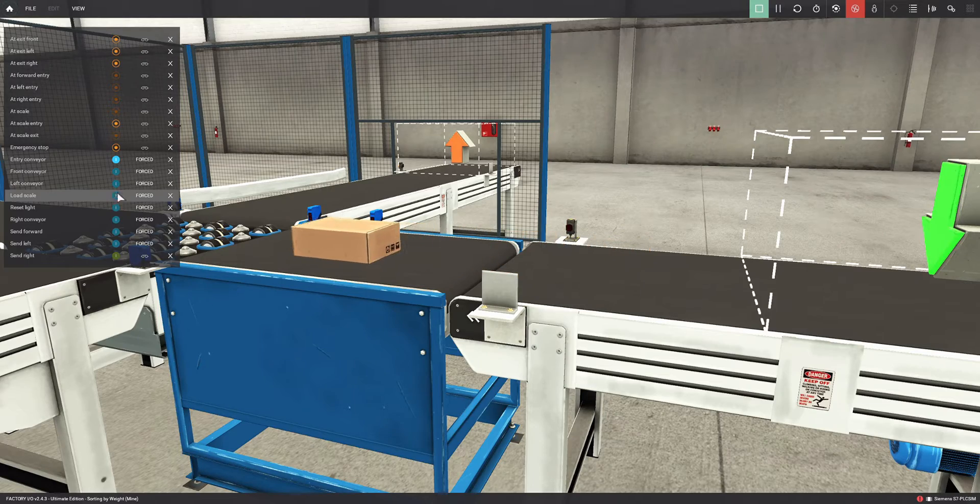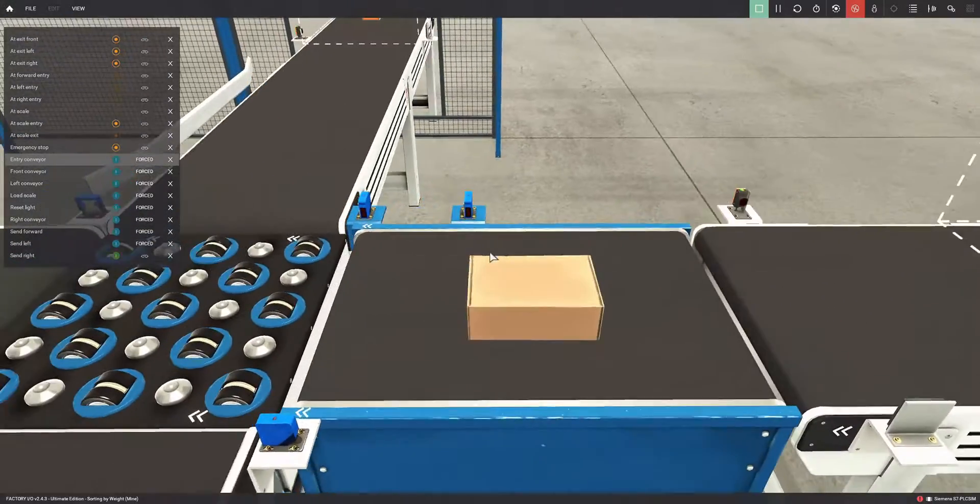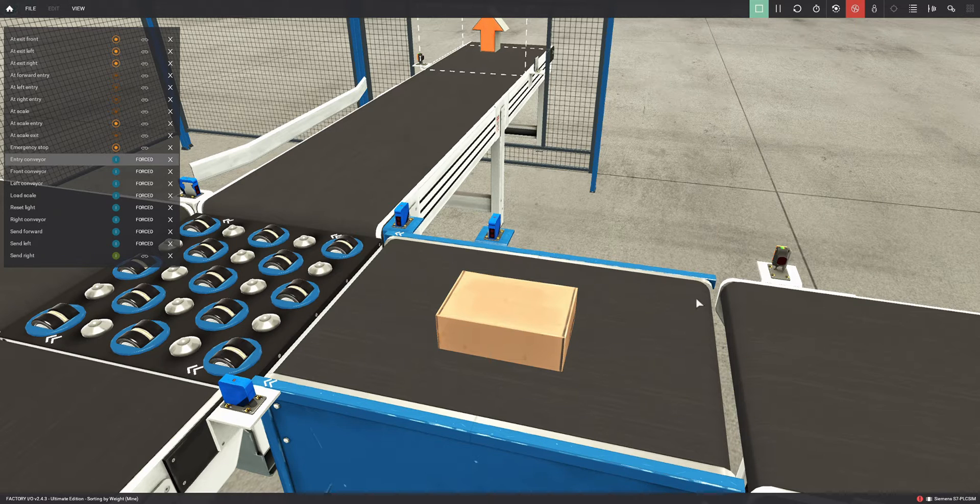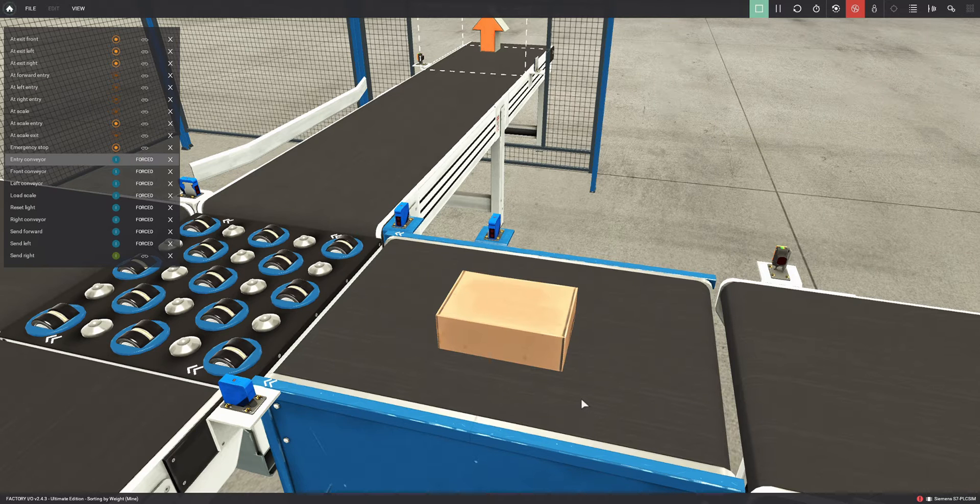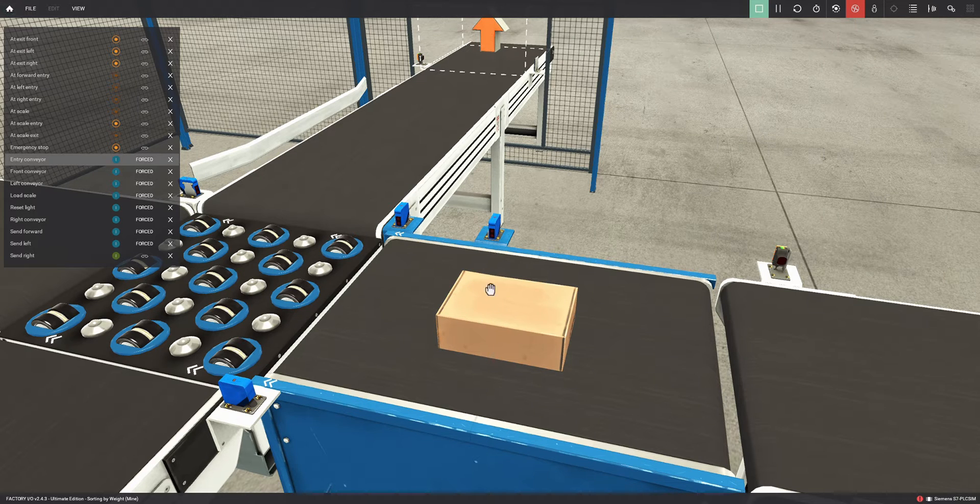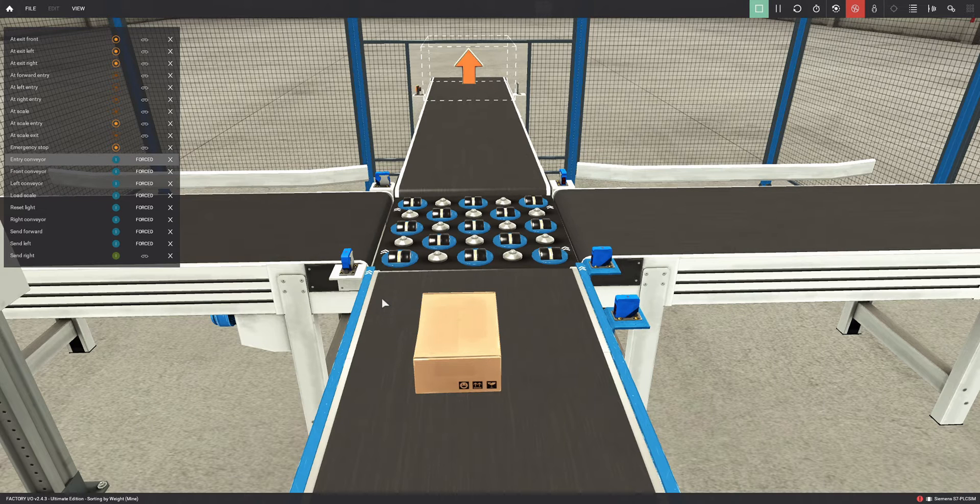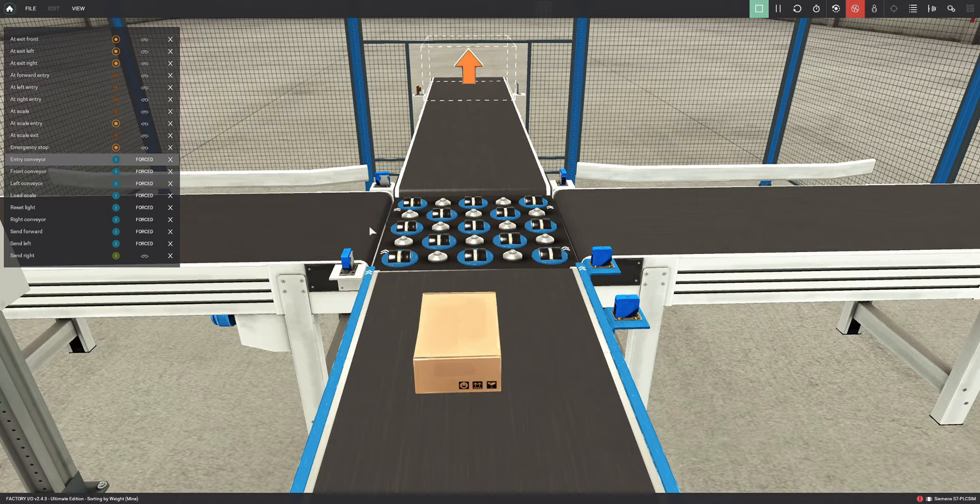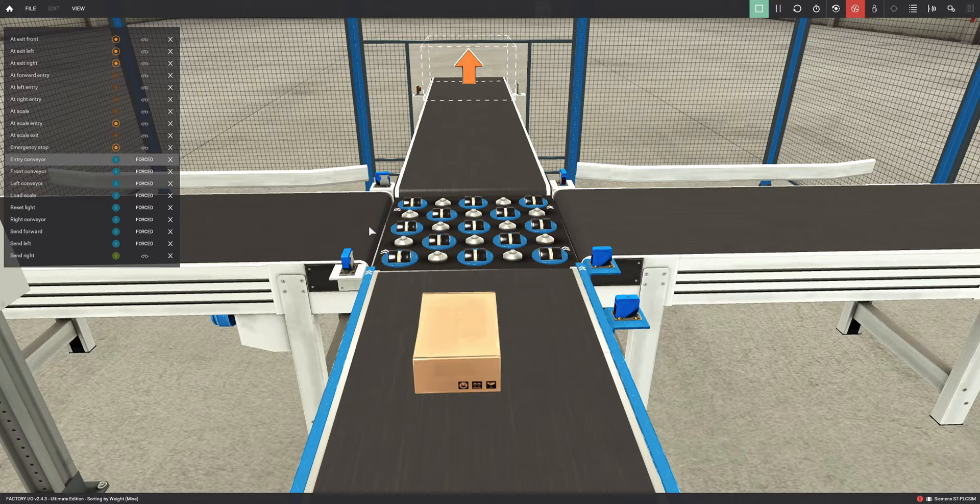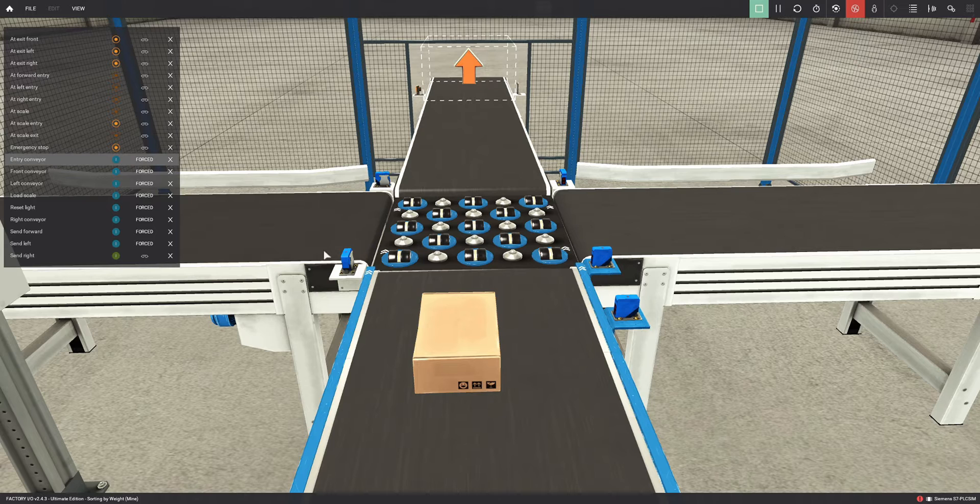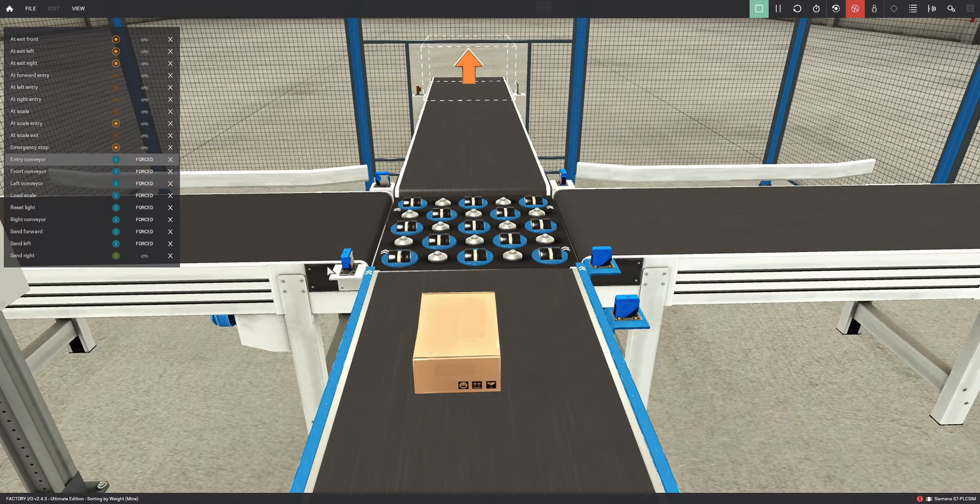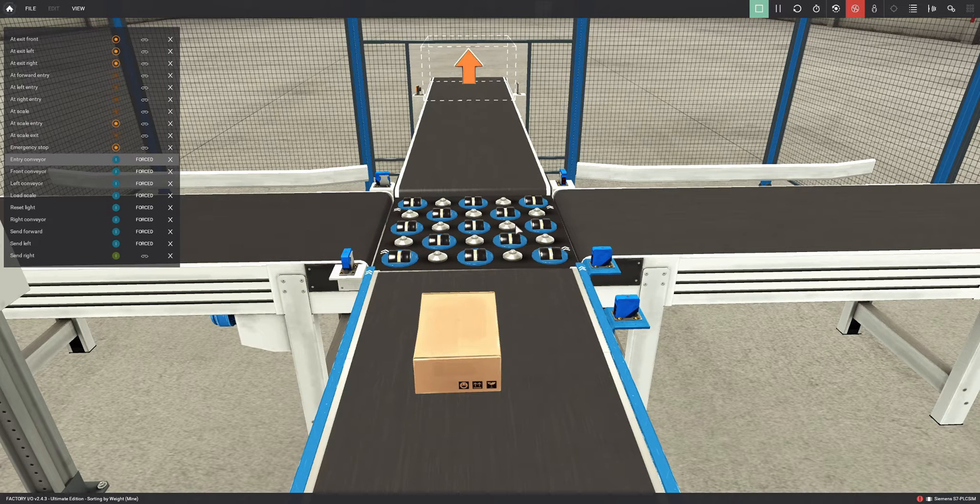When it reaches that photocell it should stop. When it arrives at this photocell here, we stop it so the object can be weighed. The weighing is actually happening once the box enters this conveyor, but since we want greater precision and when it's still it won't alter the weight, we stop the box and perform the weighing. What happens now? Well, it will give us a value between 0 and 10, actually between 0 and 7.5 which are the objects in this program. It gives me those values because I've performed the scaling. Without scaling, in the case of TIA Portal, I think the maximum is 27,648 or a similar number. But by scaling, it stays between 0 and 7.5 - between 0 and 10, which are the limits I specified.